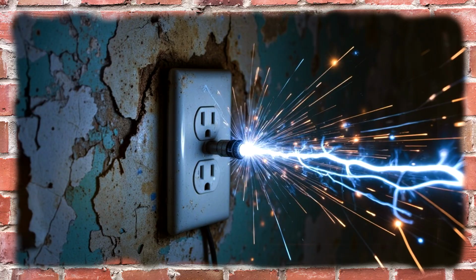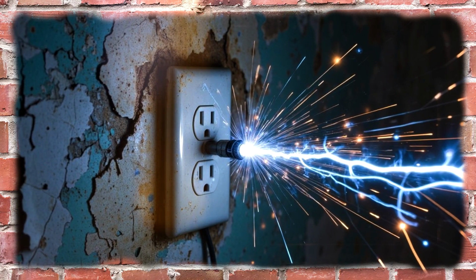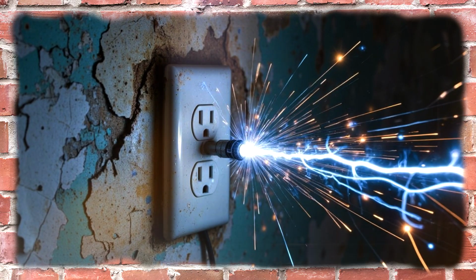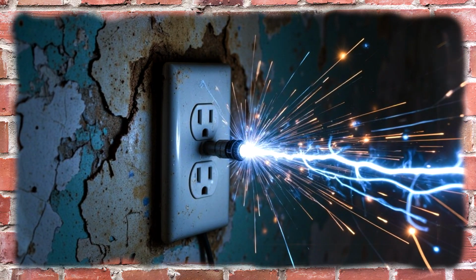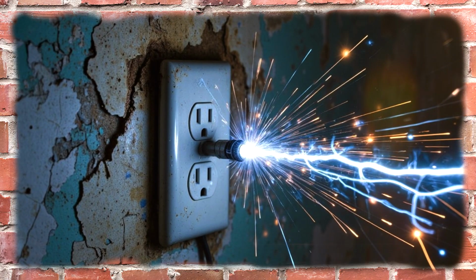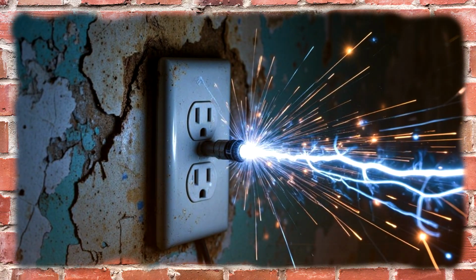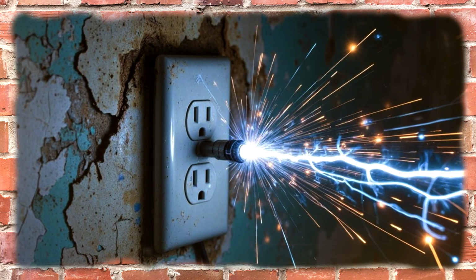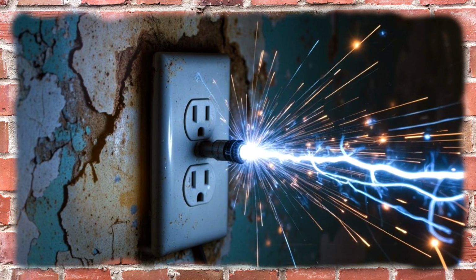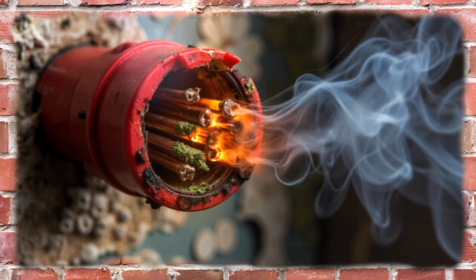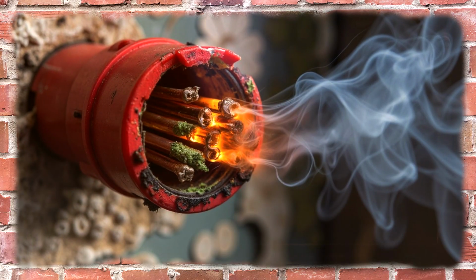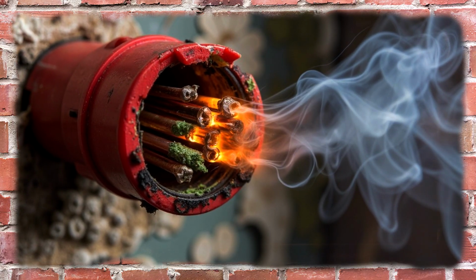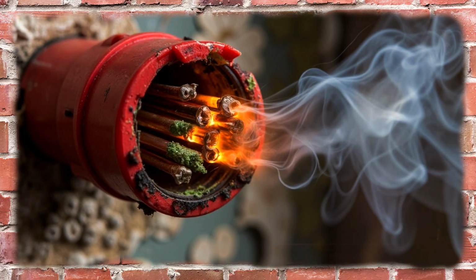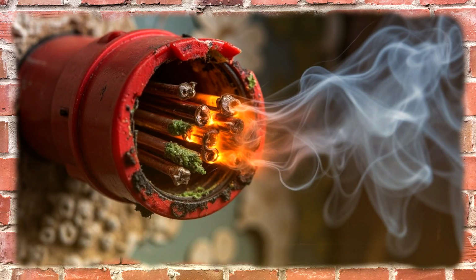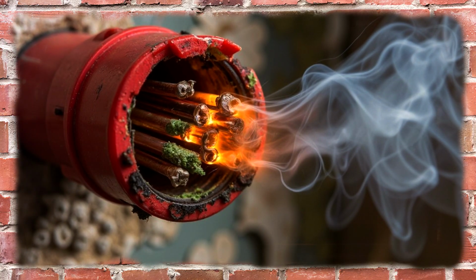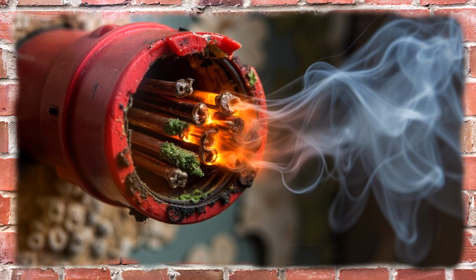Another critical aspect is insulation. In the US, the standard residential cable is NMB, non-metallic sheathed cable type B, composed of individually insulated conductors inside a shared plastic sheath, and this cable is run exposed inside walls, without conduit, because the outer sheath itself is rated for direct contact with wooden framing. Whereas in Europe and Russia, cable is typically installed inside protective conduit, PVC flexible tubing or metal sheathing, especially in load-bearing or concealed walls, due to requirements for future cable replacement without wall demolition and for fire safety, as conduit-contained cable won't propagate flame throughout a wall cavity in case of ignition.